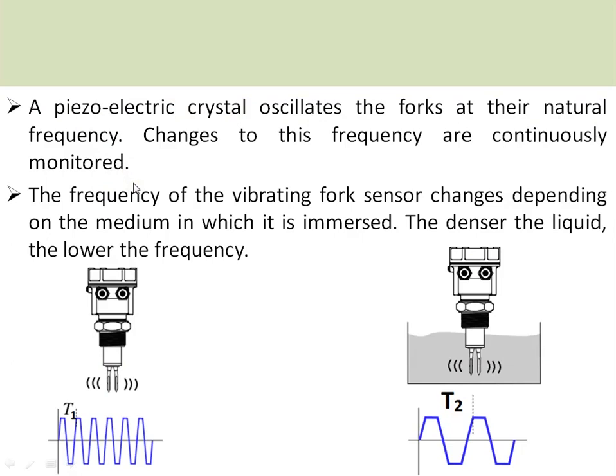To summarize the operation: a piezoelectric crystal oscillates the two forks at the natural frequency, and changes in this frequency are continuously monitored by the other piezoelectric crystal. Whenever there is no medium in contact with the forks, the frequency is high. When a medium comes in contact with the forks, the frequency of vibration decreases. The denser the liquid or medium, the lower the frequency. This decrease in frequency is monitored by the electronic circuit, which gives an output.